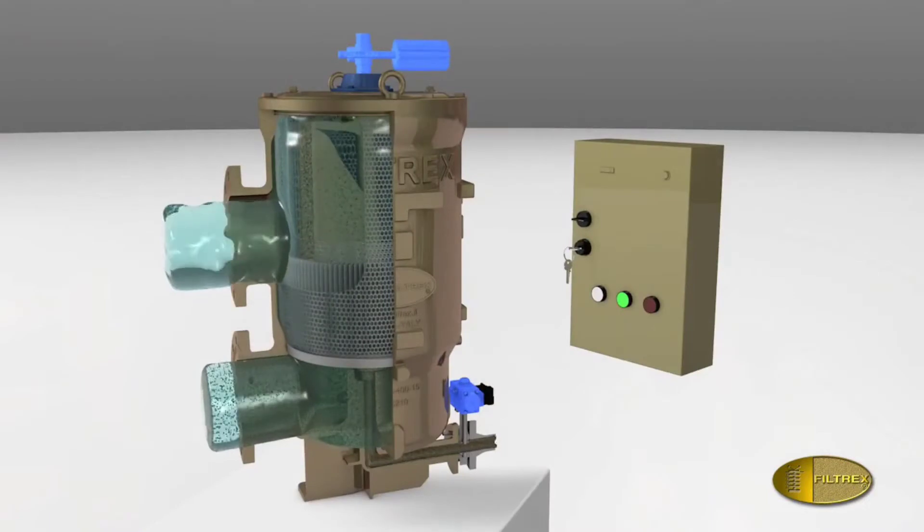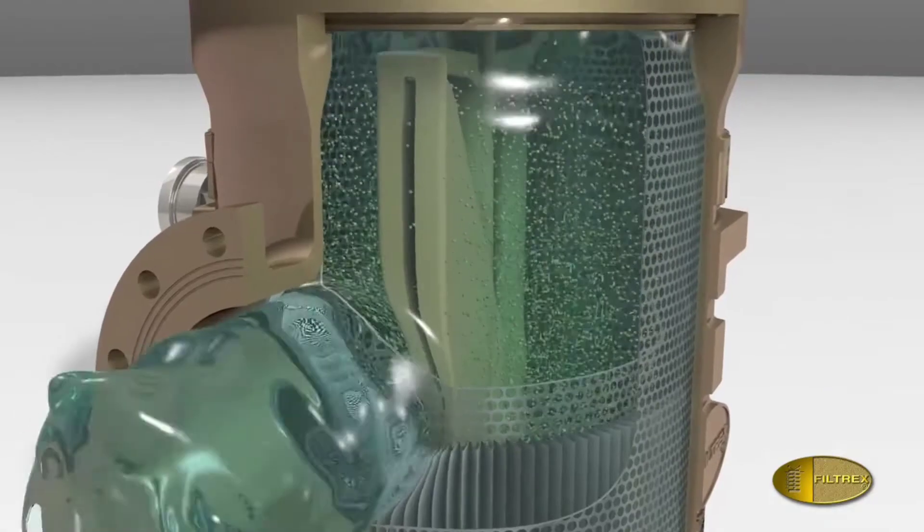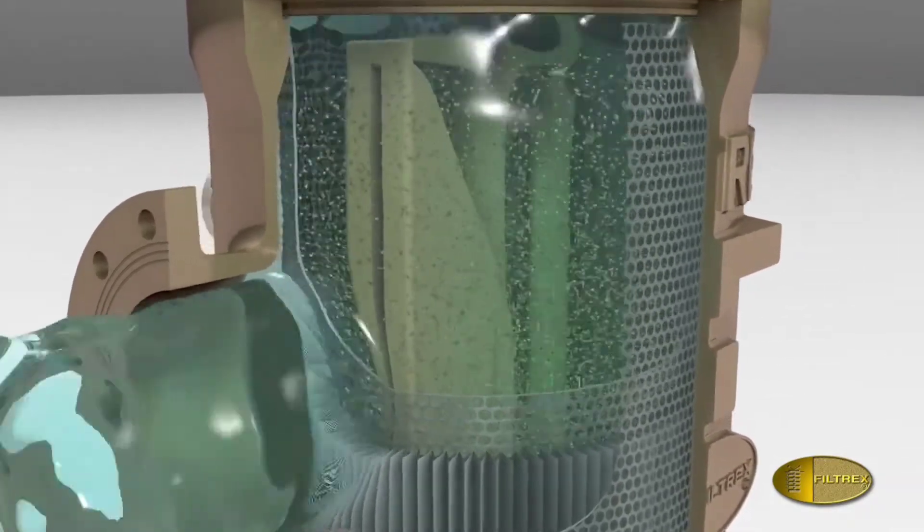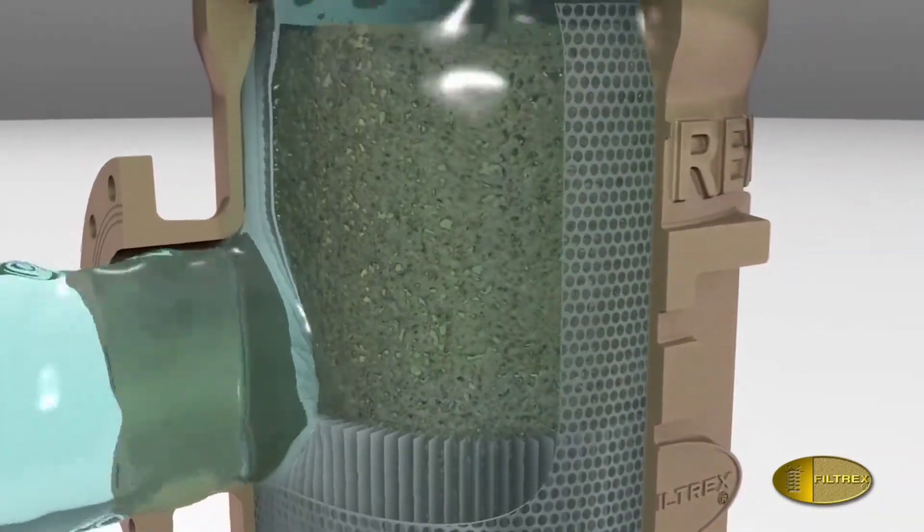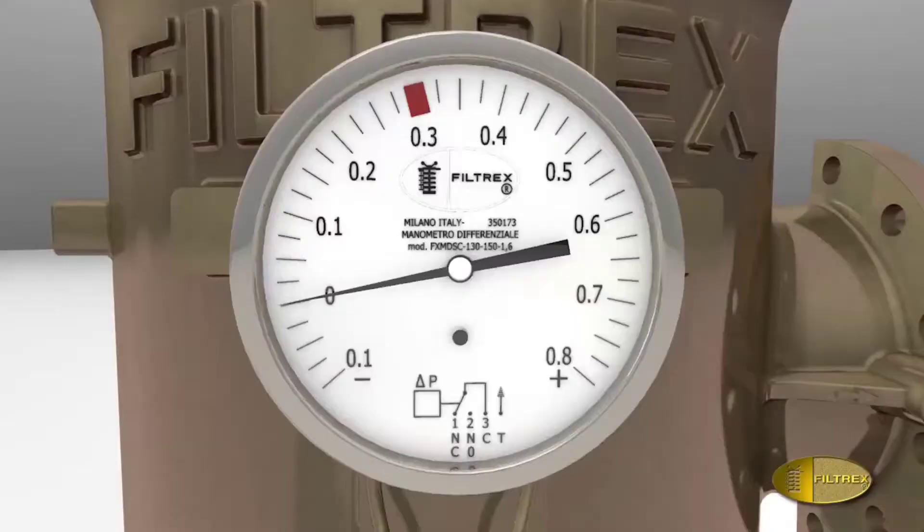At the end of the cleaning set time, the backwash valve closes and the motor stops, returning the filter to the static phase. The cleaning cycle is repeated every time the pressure drop reaches the preset value.